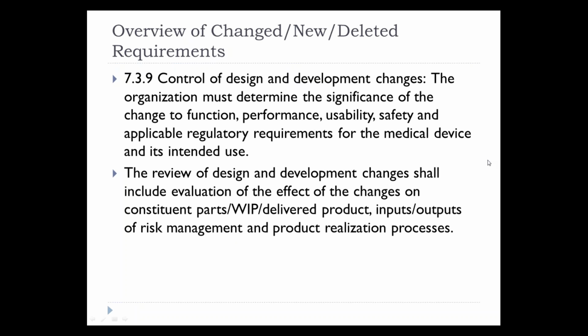7.3.9, control of design and development changes. So whenever the design changes, the organization has to determine the significance of the change as it relates to the function, performance, usability, safety, and applicable regulatory requirements for the medical device and its intended use. The review of the design and development changes needs to include evaluation of the effect of the changes on parts, WIP, delivered product, inputs, outputs to risk management, and the product realization processes. So both processes and product.